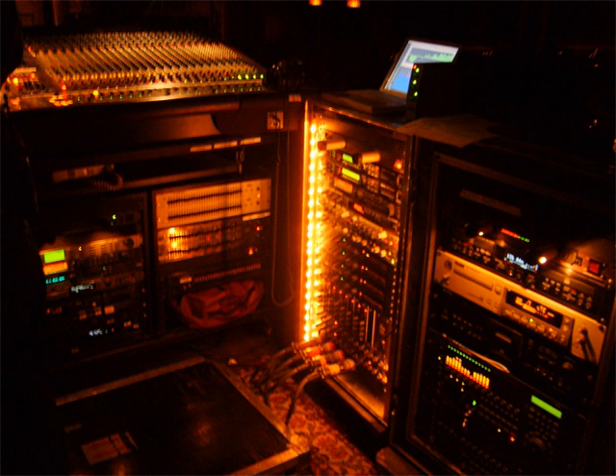When there is a large number of computers in a single rack, it is impractical for each one to have its own separate keyboard, mouse, and monitor. Instead, a KVM switch or LOM software is used to share a single keyboard, video, mouse set amongst many different computers. Since the mounting hole arrangement is vertically symmetric, it is possible to mount rack-mountable equipment upside down. However, not all equipment is suitable for this type of mounting. For instance, most optical disc players will not work upside down because the driving motor mechanism does not grip the disc.